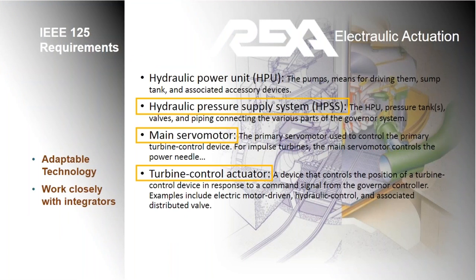Now, IEEE 125 requirements for governor controls. Multiple components can be tied to a governor control setup. So it is important to identify what REXA is for governor controls. REXA is not a governor system, but can be tied to one. A REXA is a type of hydraulic supply system. It is the secondary servo motor that operates the power needle for a dual regulated turbine, or the primary servo motor for a single regulated turbine. The REXA is also the turbine control actuator that can be integrated into a governor control system. And although REXA is not a governor, it can be adapted for multiple types of control configurations.